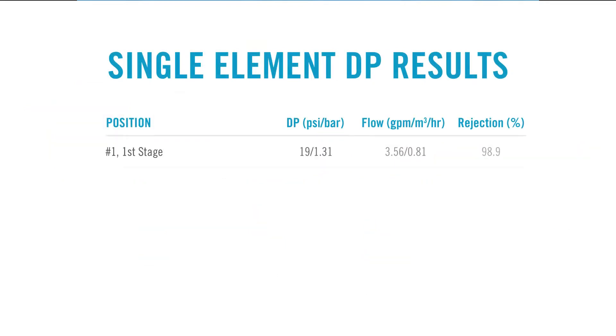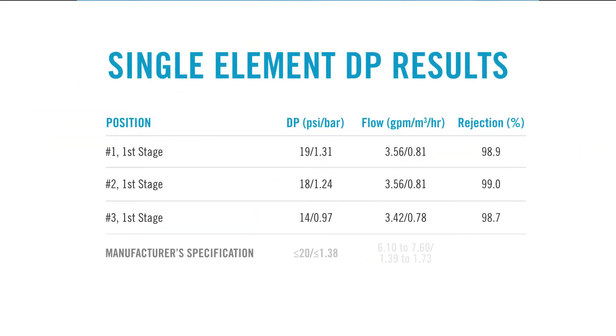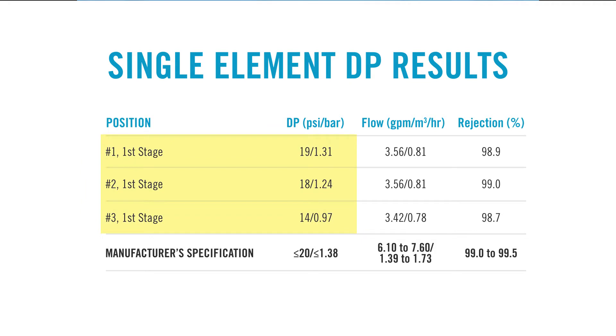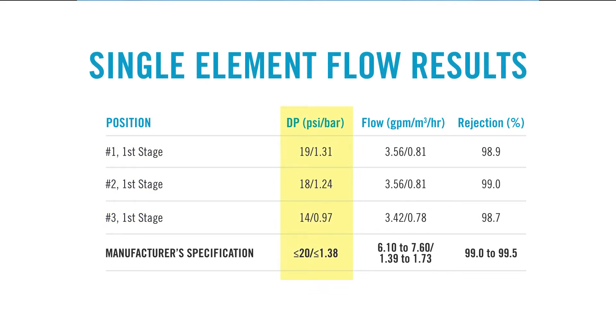As increased delta pressure was observed in the first stage of the RO system, the site sent the first three elements from the first stage for individual performance testing at the Avista facility. This gave us a performance snapshot to determine which elements were most affected by the fouling problem. We see that the delta pressure is highest for the first element in their first stage, and as you travel through the system, the delta pressure becomes more manageable, even though it's still elevated. We expect delta pressure of clean elements to be between 3 and 5 psi.